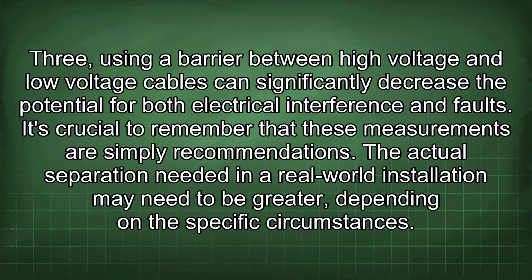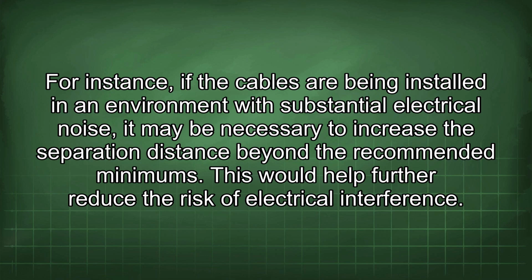The actual separation needed in a real-world installation may need to be greater, depending on the specific circumstances. For instance, if the cables are being installed in an environment with substantial electrical noise, it may be necessary to increase the separation distance beyond the recommended minimums. This would help further reduce the risk of electrical interference.